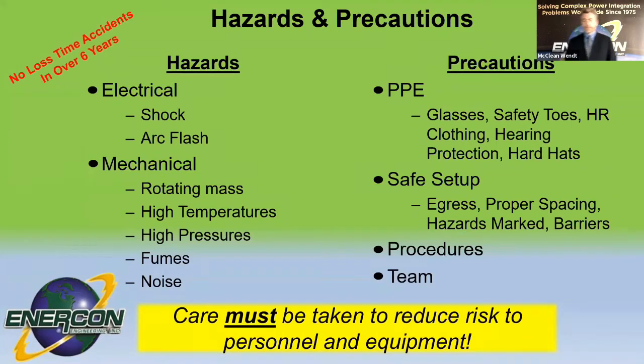So first and foremost, we put safety ahead of everything else. We want to make sure that everyone goes home safely and no one's injured. And in testing these unproven systems, there are a lot of dangers and hazards. There's electrical hazards or shock, in the worst case, electrocution, arc flash, which can cause explosions. And then we also have lots of mechanical dangers with rotating mass that can either throw parts or personnel can get caught up in the equipment. There's high temperatures, high pressures, fumes, and also they're very noisy when we're testing. So all of these need to be addressed, and we need to take measures to mitigate risk to both personnel mainly, and then secondarily to reduce the risk to the equipment, both the testing equipment and probably more importantly, the customer's product.